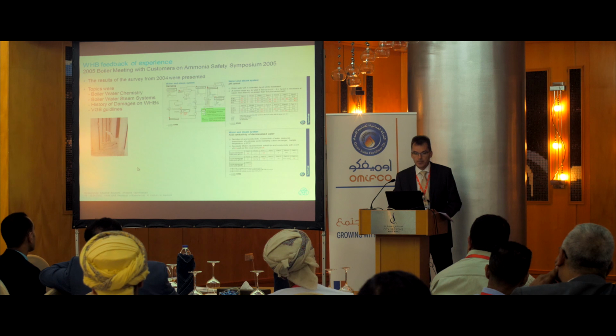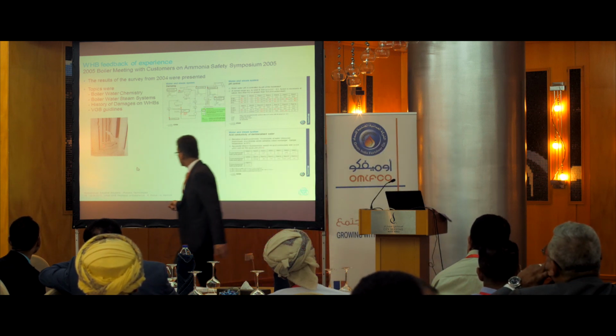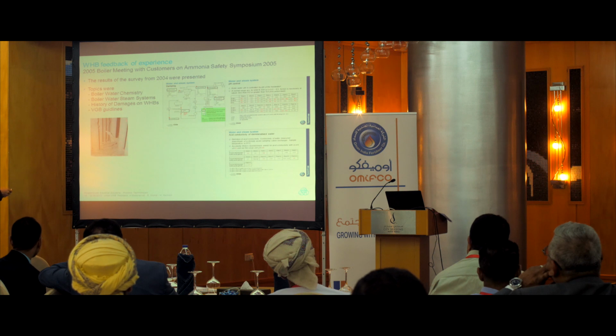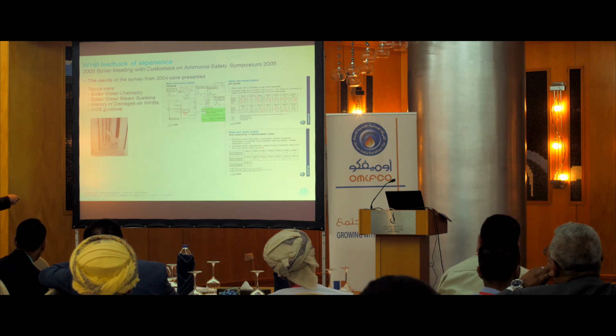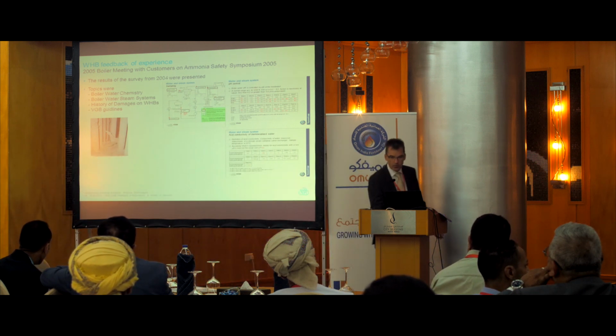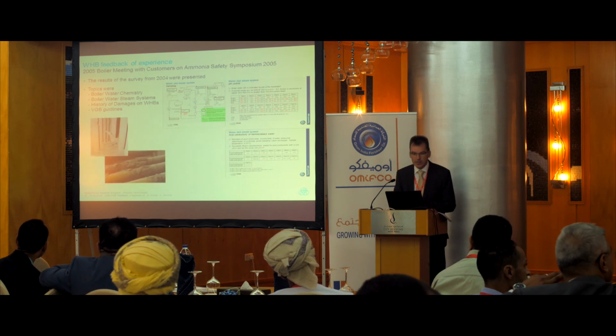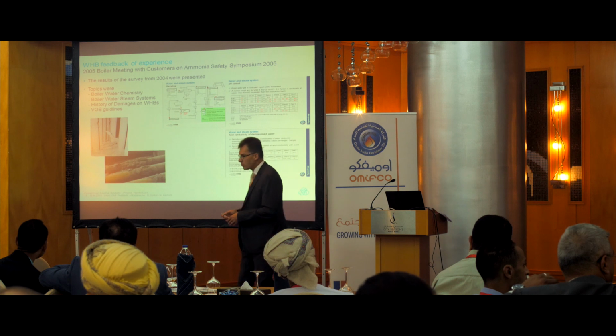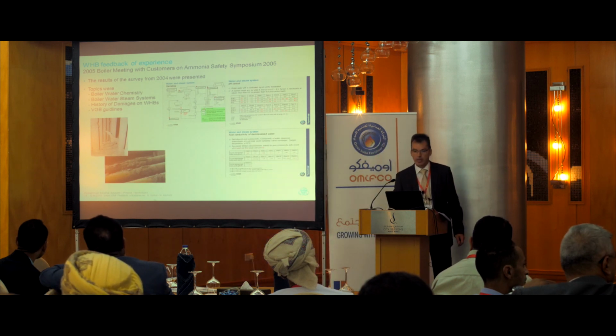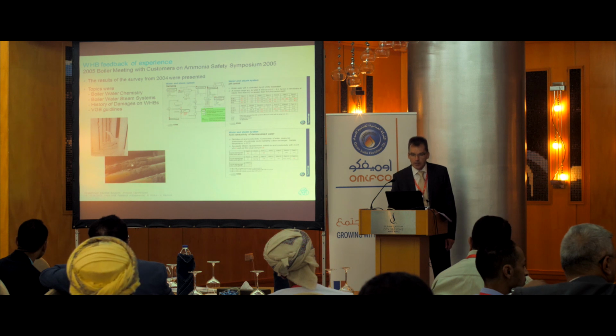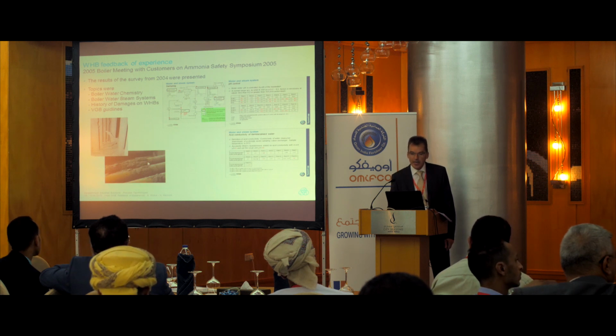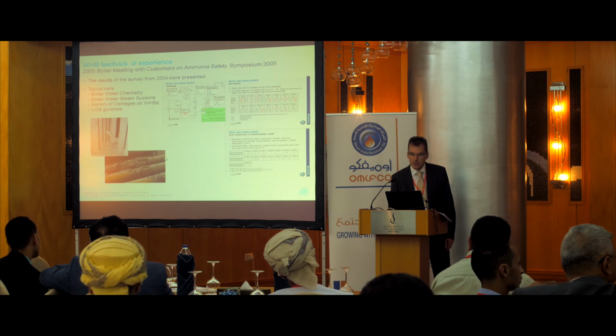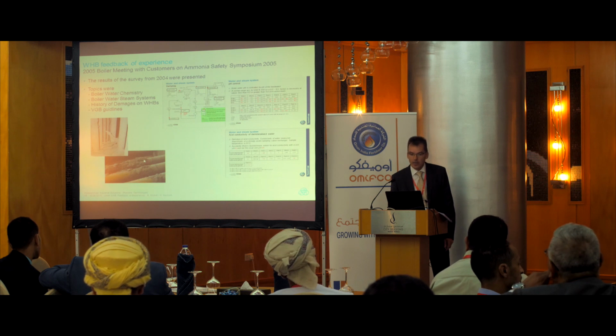You see here the tube sheet on the bottom, the heat exchanger tubes going upwards, and here flakes, layers. Later on we knew that these are oxide layers. Also you can see it on the tubes themselves. You see here these deposits on the tubes. It's also interesting on the right side where there are no deposits, and this is applied to the tube sheet. There are the ferrules located inside, which keep the temperature lower. As soon as the ferrule ends, we have a higher temperature and the deposits will be deposited there.